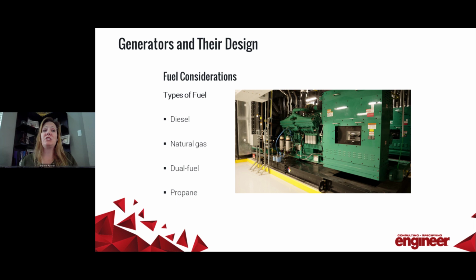So diesel, as I mentioned, is the most common for emergency engines because it's very reliable. The advantages of diesel include that it's able to start in 10 seconds as required for those level 1 systems. It provides on-site storage, which is required for hospitals and many other types of facilities. The equipment's typically less expensive than natural gas historically. I mean, anything's out the window right now when it comes to cost, but historically diesel has been less expensive. And they're also really rugged and reliable. They last a long time.